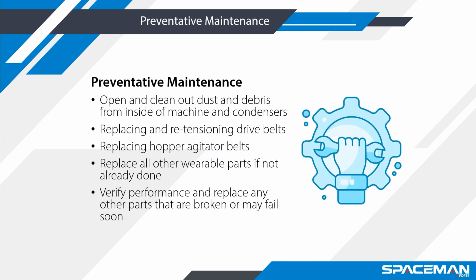During a preventative maintenance, we recommend having a service technician perform the following. First, clean out the condensing coils of dirt, dust, and debris. This keeps the refrigeration system running at peak performance and prevents expensive components like compressors from failing. Next, we recommend to inspect and tension or replace all internal belts, such as the main drive belt, as well as the hopper agitator belts.